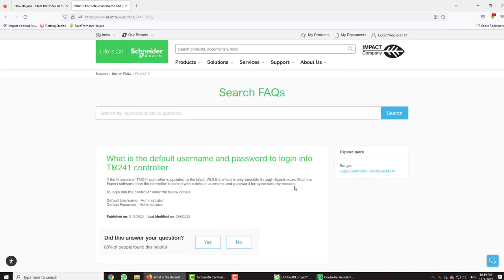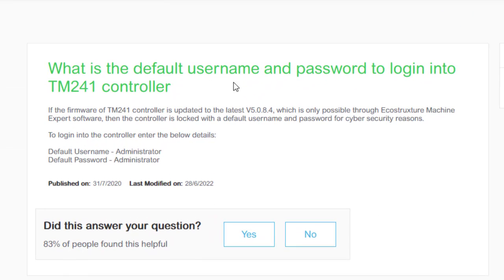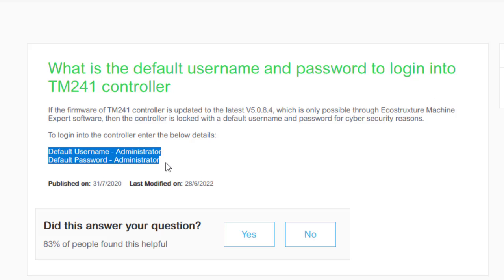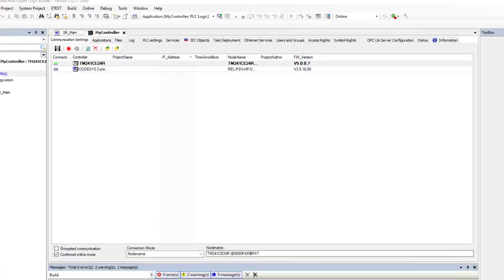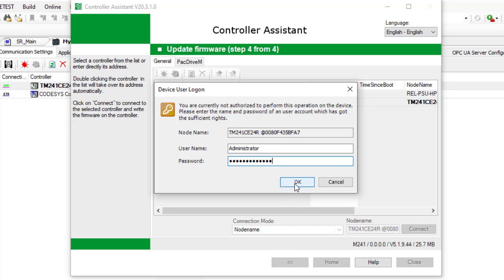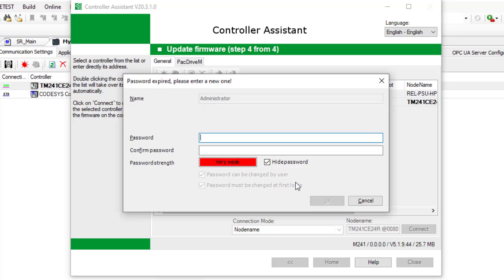We are prompted for user login information because updating firmware is a serious operation and should not be accessible to everyone. For the first time using a Schneider PLC, the default username and password are both 'administrator,' as stated on the Schneider website. We enter 'administrator' as both username and password and press OK. Since it's the first use, we are required to set a new password — we choose a new secure password and press OK.